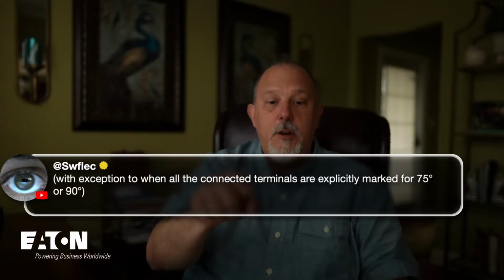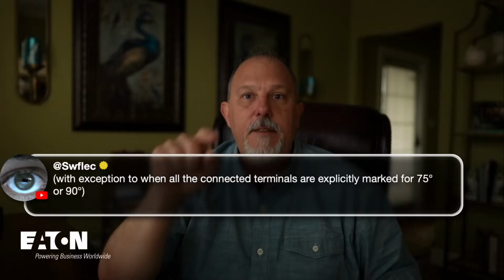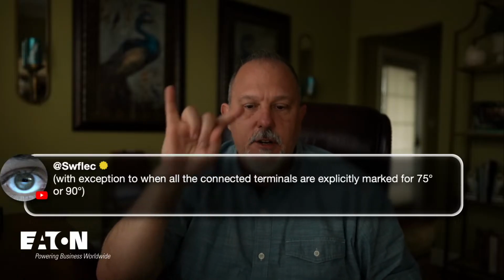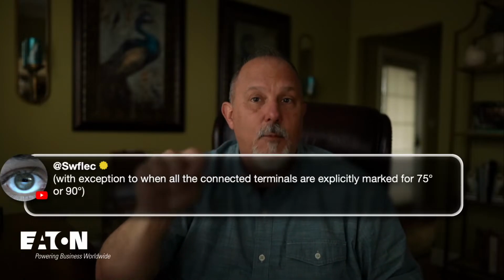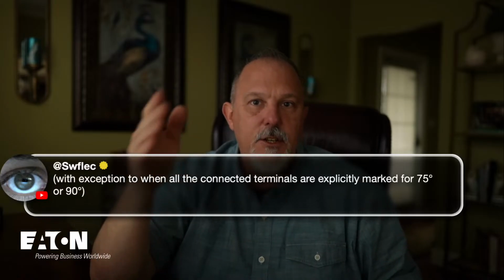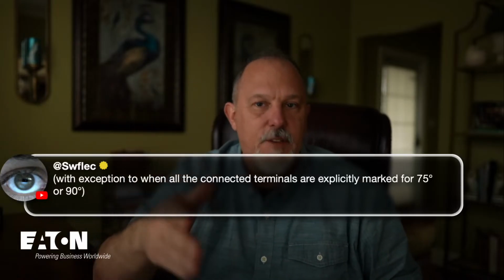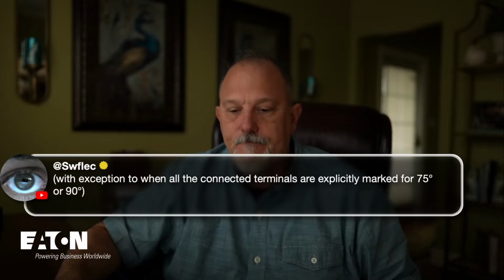Now, my point though was that even if both terminations are 75 degrees C, if I'm using NM wire, I can't use the 75-degree C column, I have to use the 60.